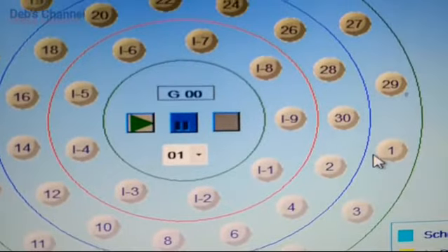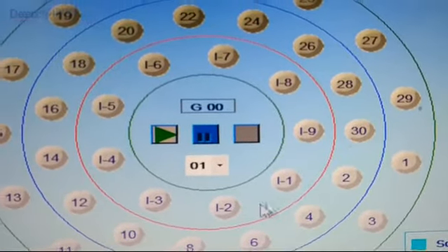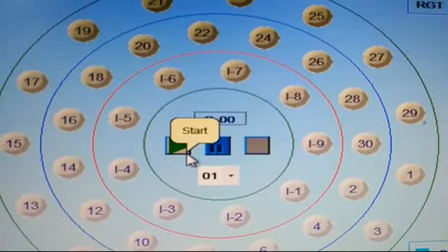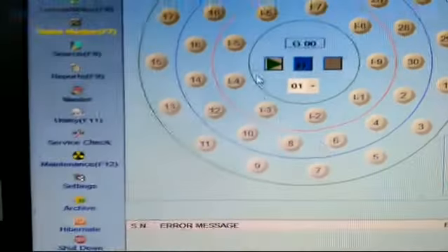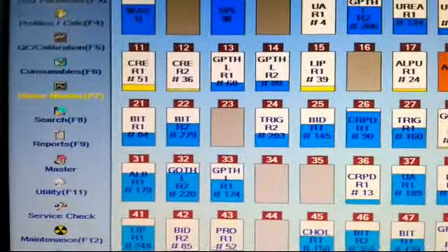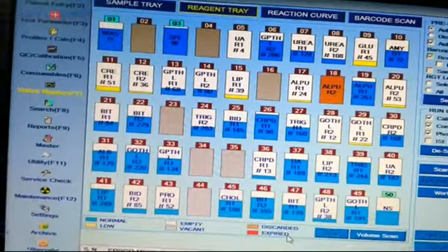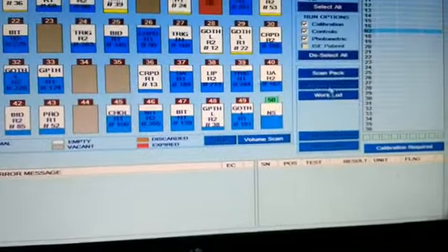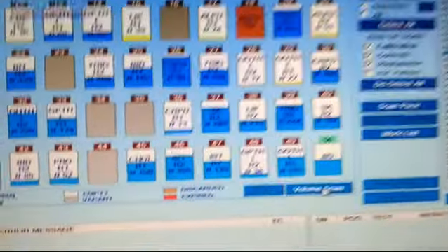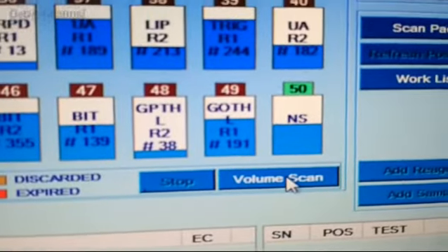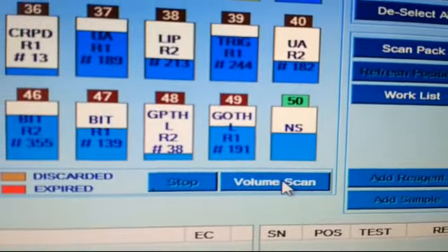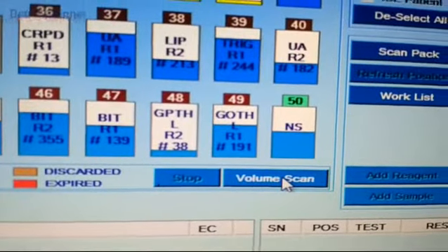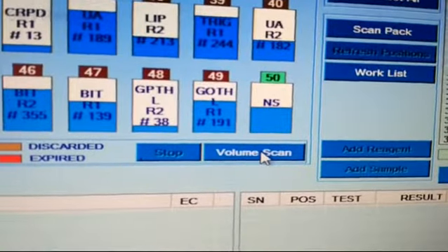In the F7 or the status monitor, there is the sample position showing, like 1, 2, 3, 4 zigzag positions. You have to program the sample, and then we have to press the start button. But in the morning, we have to run the volume scan of the reagent to know the reagent status. This is the volume scan. Whenever we perform the volume scan, the machine will display the status of the reagent, like the tests remaining or whether the reagent is required or not, etc.